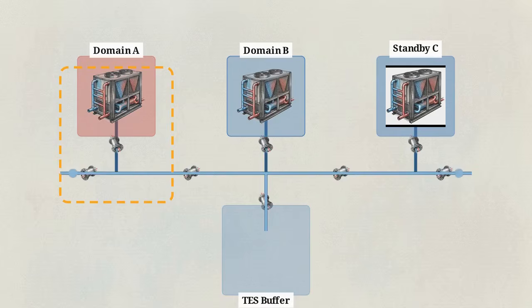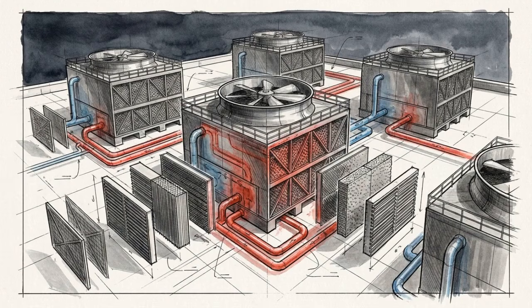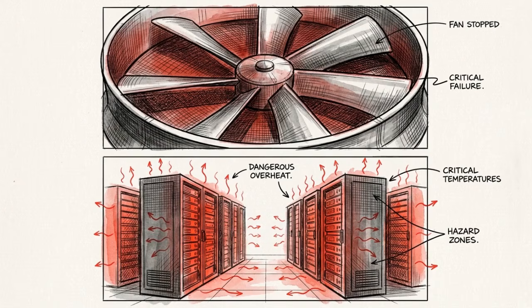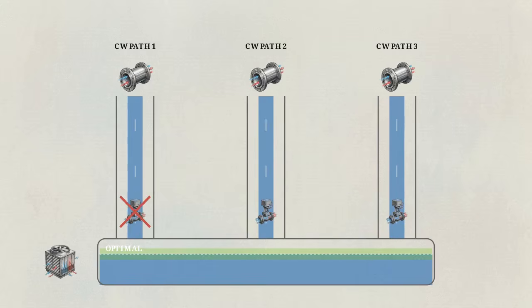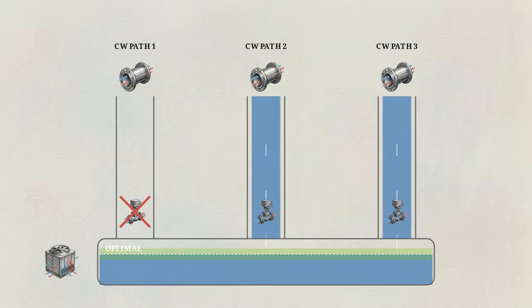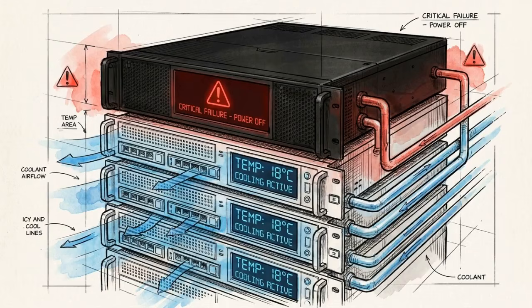Another critical failure mode occurs when heat rejection is suddenly constrained, such as losing a cooling tower cell while the facility is under full IT load. The escalation response requires maximizing flow through the remaining condenser water paths and verifying tower basin levels. IT load shedding is executed only if thermal maximums in the data hall are definitively breached.